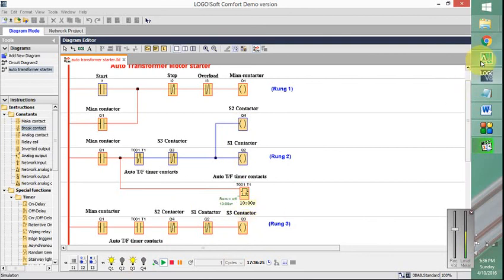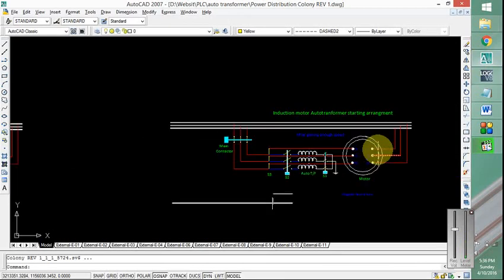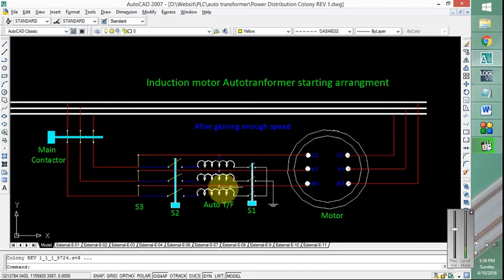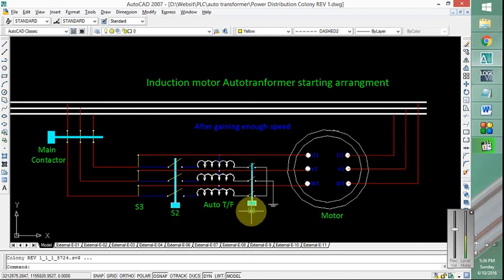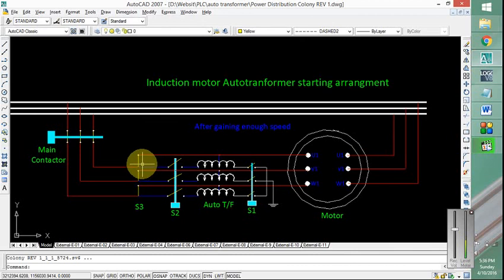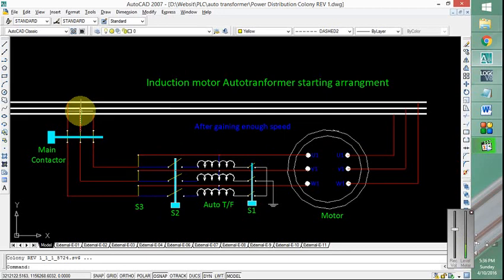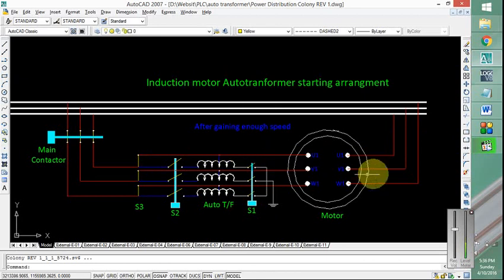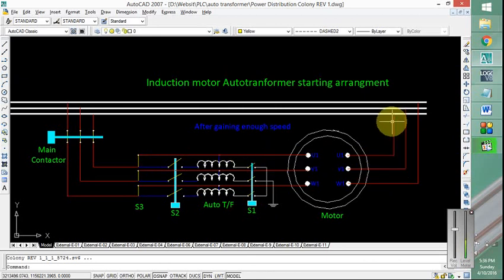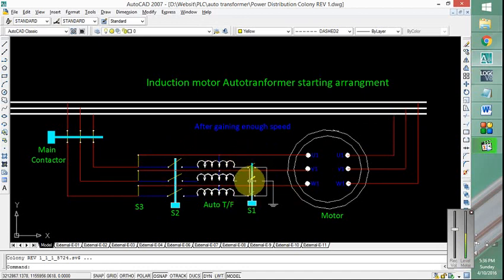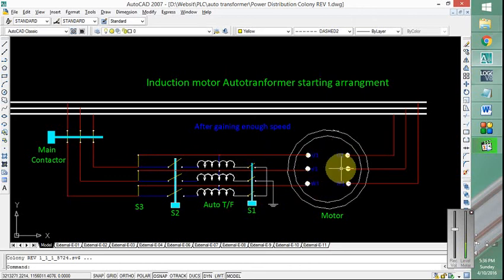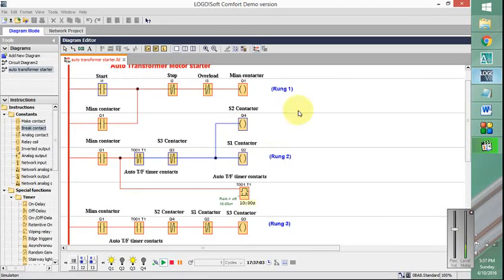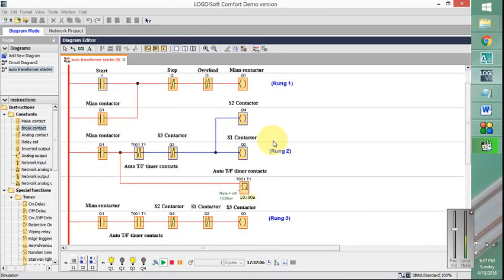When this happens, as you can see S2 and S1 are now de-energized, switches are open, while S3 is energized and it closes the switch. And now the current from the supply goes through this path bypassing the auto transformer into the motor and back to the supply. So now the auto transformer is bypassed and full voltage is applied to the motor. So in this way we can achieve the auto transformer motor starter. This 10 seconds delay depends on the user requirement.